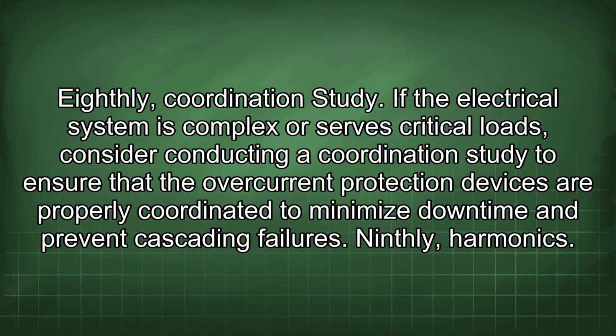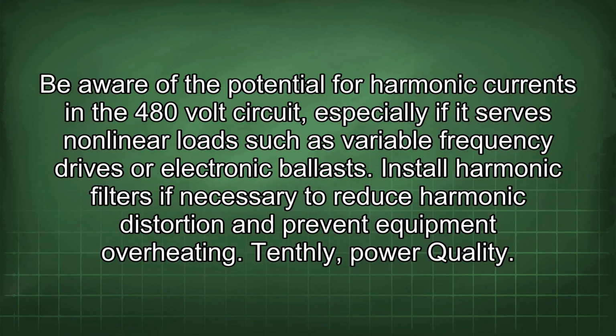Eighthly, coordination study. If the electrical system is complex or serves critical loads, consider conducting a coordination study to ensure that the overcurrent protection devices are properly coordinated to minimize downtime and prevent cascading failures. Ninthly, harmonics. Be aware of the potential for harmonic currents in the 480-volt circuit, especially if it serves nonlinear loads such as variable frequency drives or electronic ballasts. Install harmonic filters if necessary to reduce harmonic distortion and prevent equipment overheating.